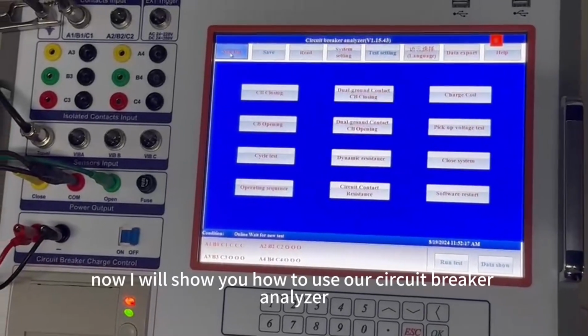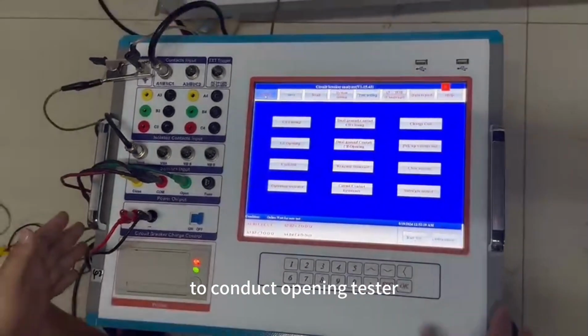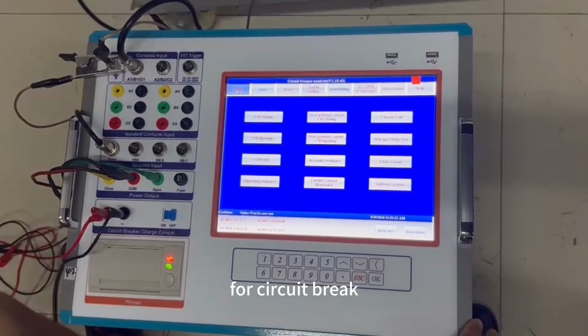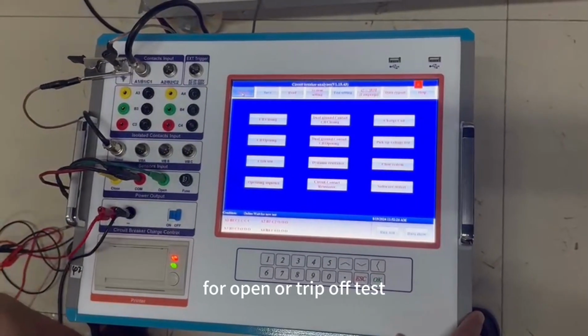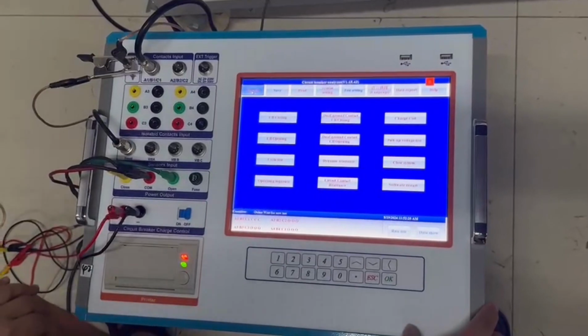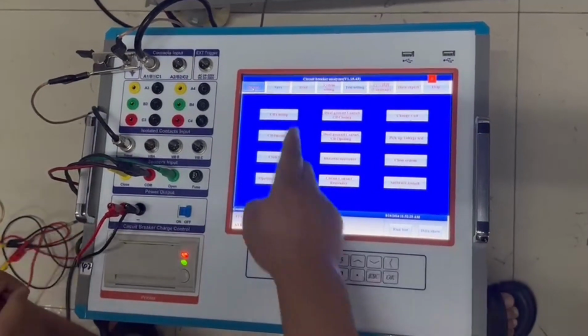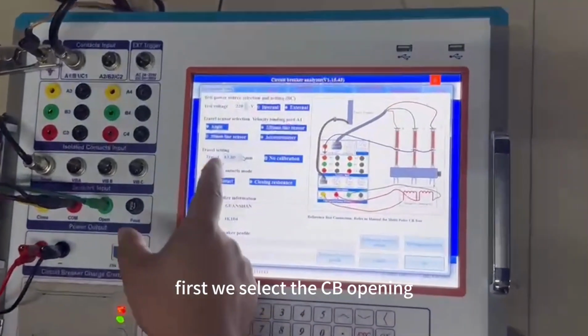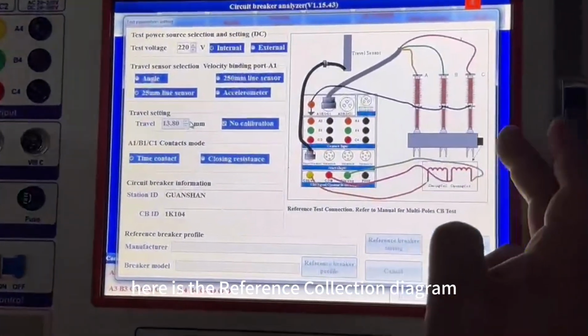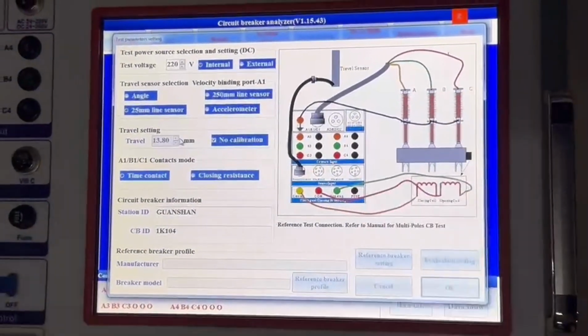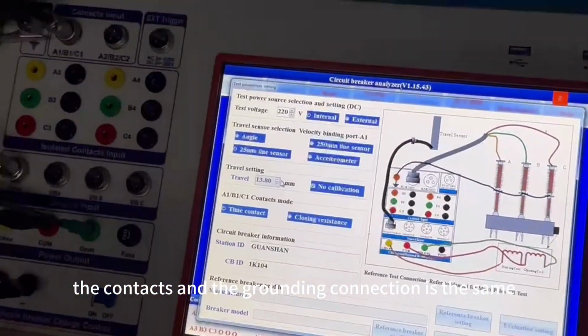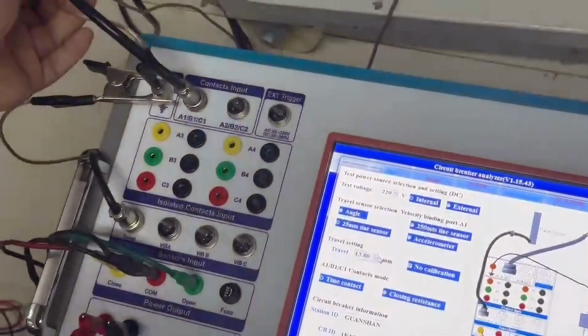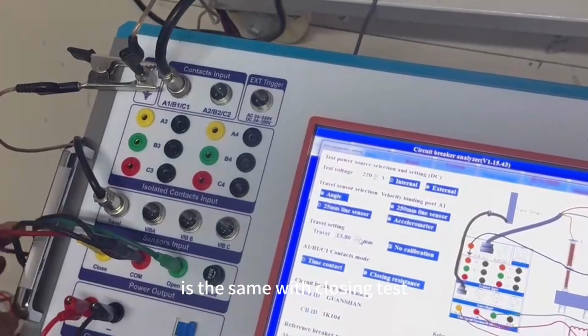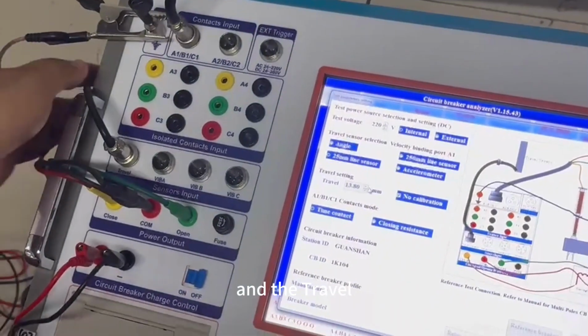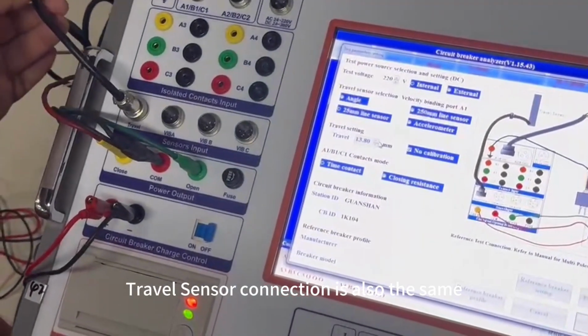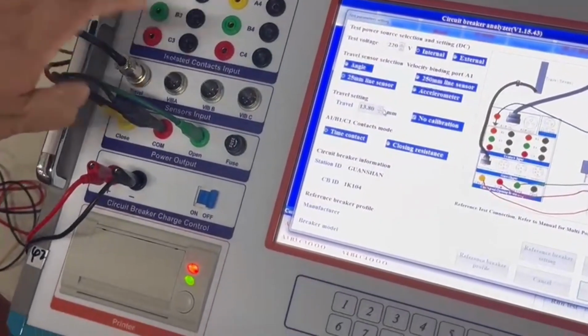Now I will show you how to use our circuit breaker analyzer to conduct the opening test for a circuit breaker. For the opening or trip off test, first we select the CB opening. Here is the reference connection diagram. The contacts and the grounding connection are the same as the closing test, and the travel sensor connection is the same as the closing test.